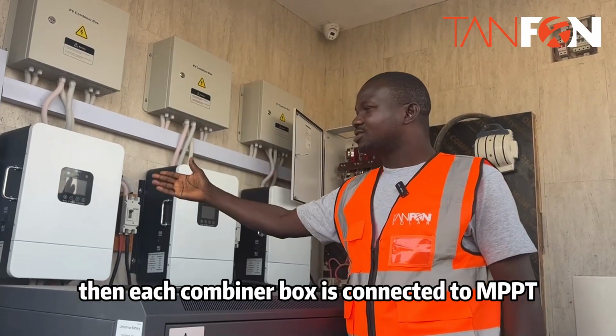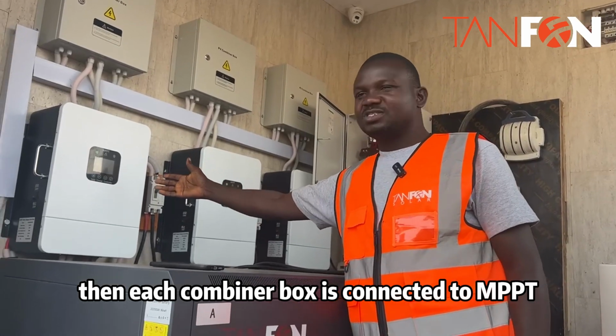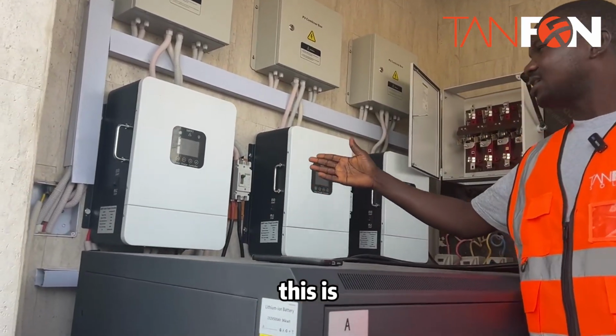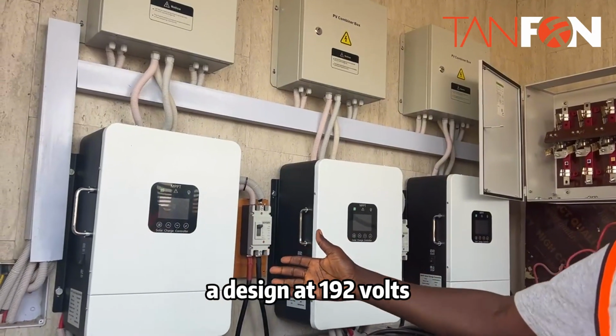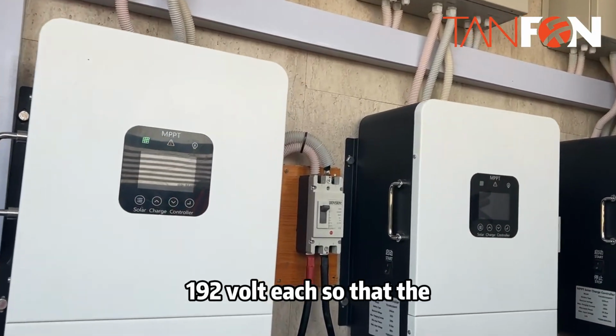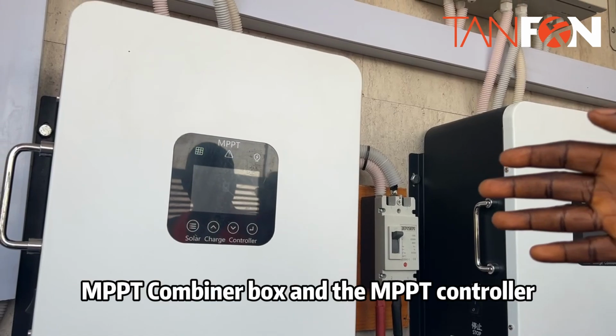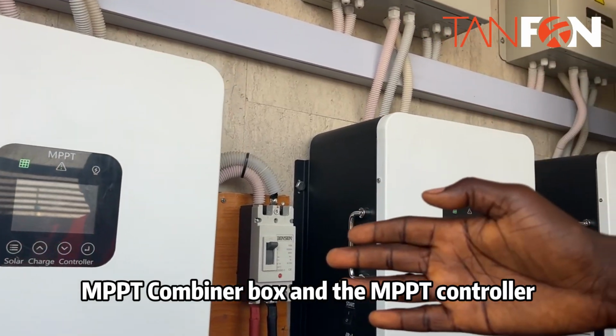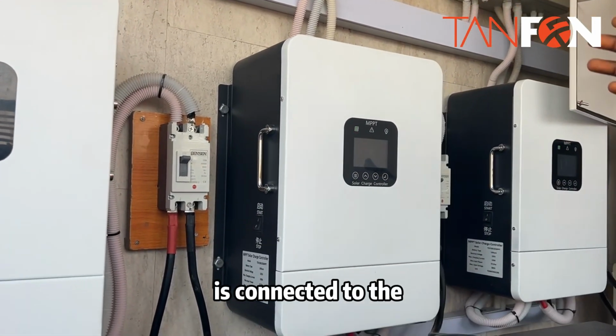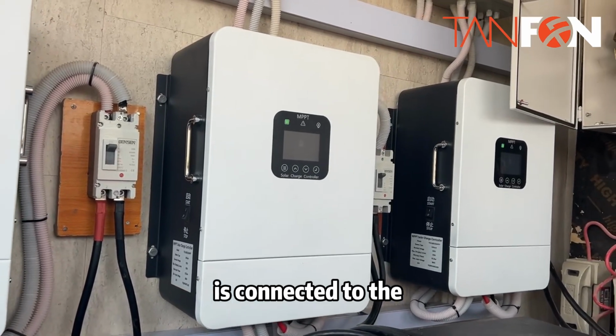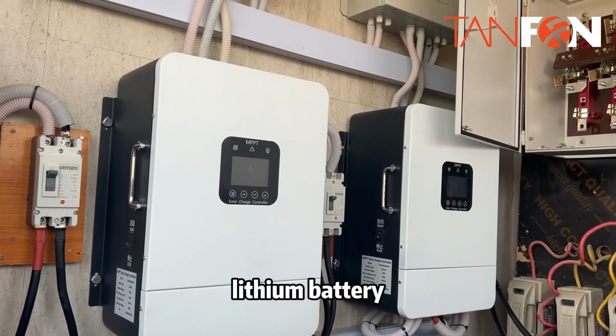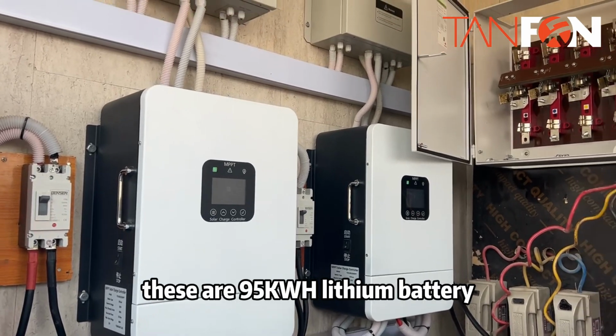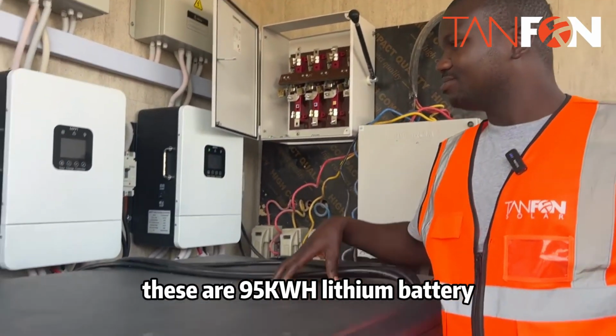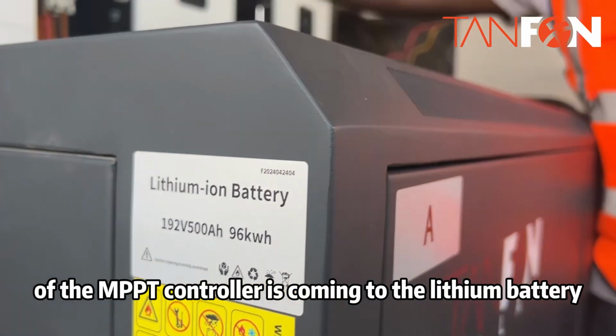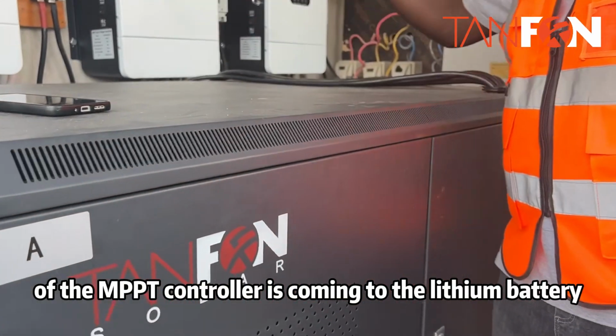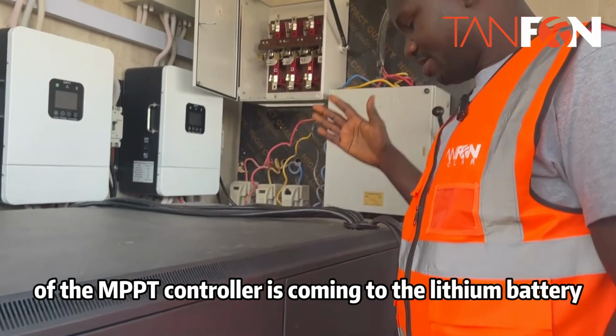Each combiner box is connected to an MPPT charge controller at 192 volts each. The MPPT controller is then connected to the lithium battery, which is a 95 kilowatt hour lithium battery. Each string from the MPPT controller comes to the lithium battery.